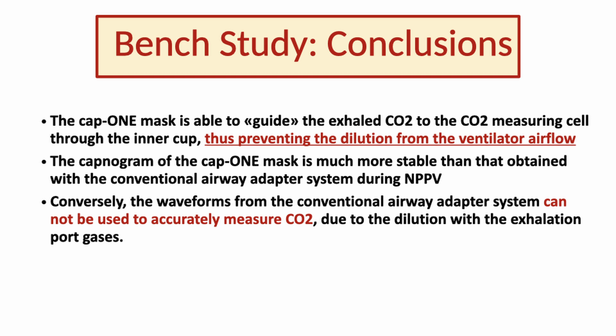The conclusion of this first bench study is that the cap-ONE mask is able to guide the exhaled gas to the CO2 measurement cell through its inner cup, thus preventing dilution. The capnograms obtained with the cap-ONE mask technology are stable and absolutely reliable. Conversely, those obtained from the conventional airway adapter system are unreliable.